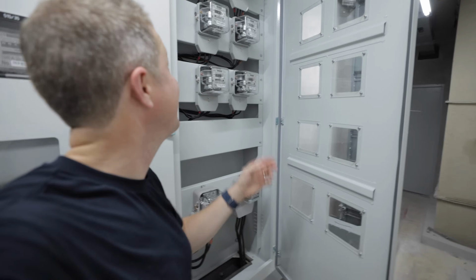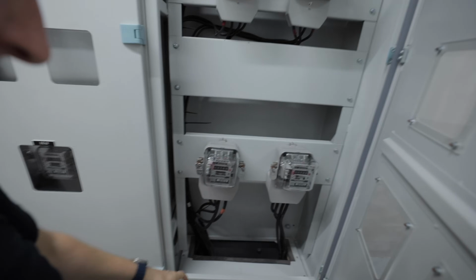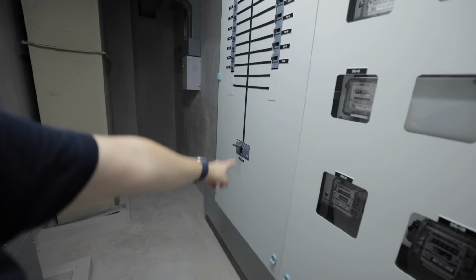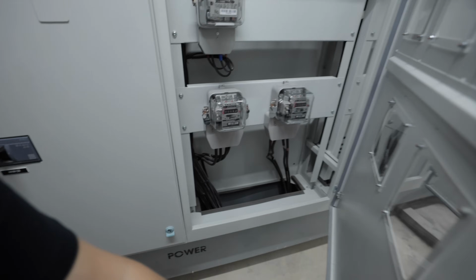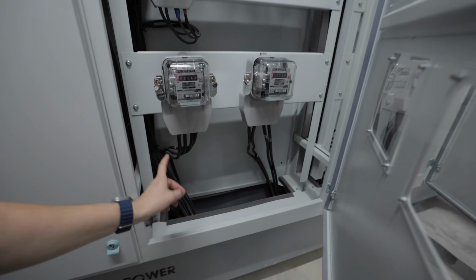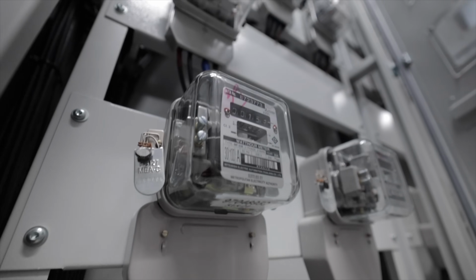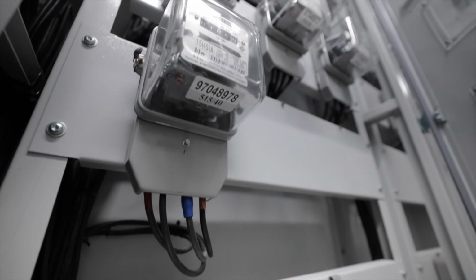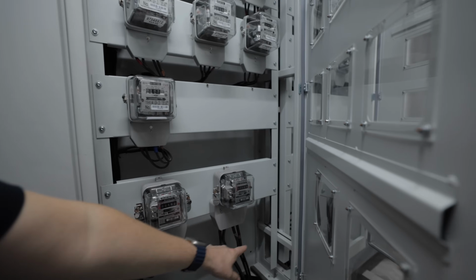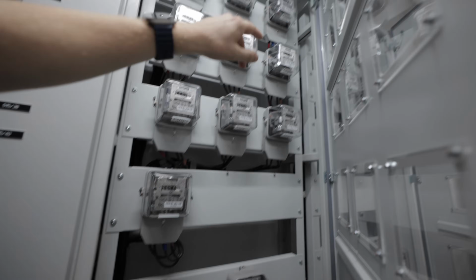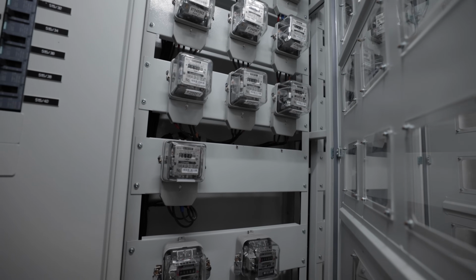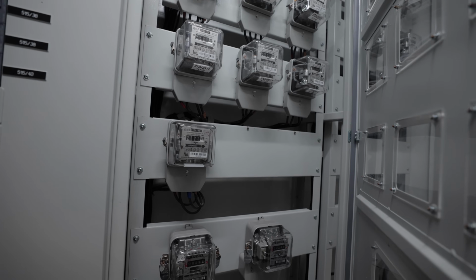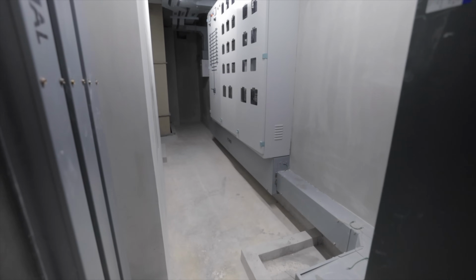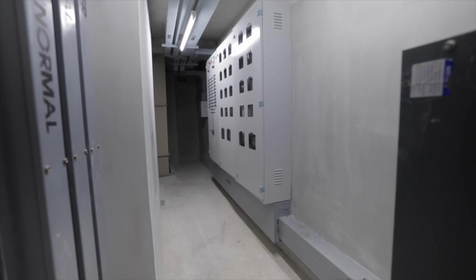Now here we get a naughty sneak peek inside. I'm being very careful not to go anywhere near any live parts, but you can see that, presumably out of the bottom of that board, these cables come and then loop up and through the meter - two wires going in and two going out, so live and neutral in, live and neutral out essentially. Bizarrely, these two have quite thick wires, whereas these ones have smaller wires. I'm not quite sure why, whether these two have a slightly larger supply, but it's really interesting to see the inner workings of a Thai apartment board.